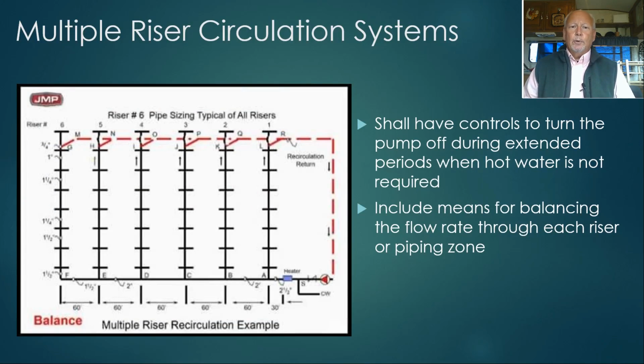If you have a multiple riser circulation system, for example, in R2, a multifamily building with a central water heating system, or in a hotel motel where you have multiple risers distributing hot water to the fixtures in the building, you again need to have controls that will turn the pump off during extended periods when hot water is not required. That can either be a time clock or aquastat, as we mentioned earlier. But you also need to include the means for balancing the flow rate through each riser or piping zone. Now, this is fairly common practice, but the code has added this language that you need to have a method of balancing the flow through each riser.